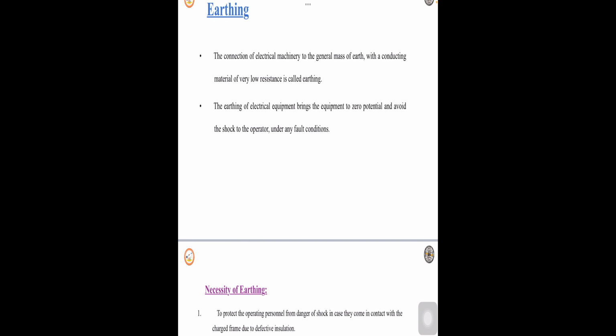There are certain objectives of earthing which we must remember. The earthing objectives are to save human life from shock by blowing the fuse of any apparatus which becomes leaky. That is, whenever it is leaky or faulty, the earthing will protect human life against electrical shock. It will provide safe operation. We can save the conducting material and protect high-rise buildings from atmospheric lightning. Whenever lightning occurs, earthing will protect us from the high voltage lightning and maintain the line voltage constant.